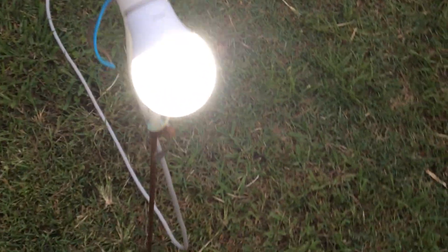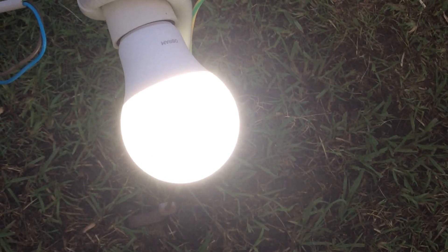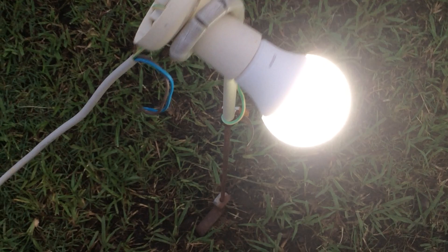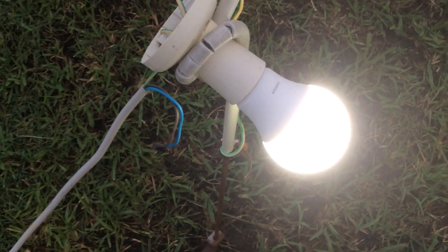It appears to now be flashing. Again, that's a frequency issue. If I was to tip some water into that, or find an area that has more water in the ground, we might avoid that flashing. That seems to have taken care of it — so it can be controlled by tipping a couple of liters of water around the electrodes at both ends.